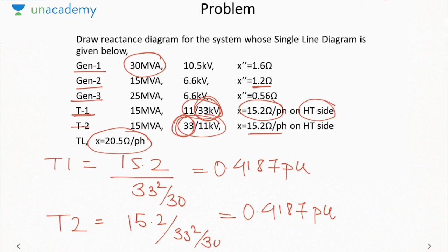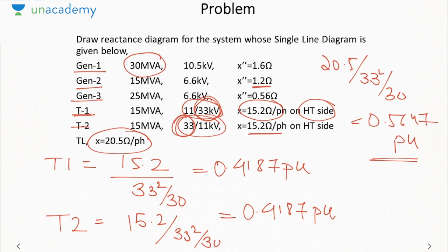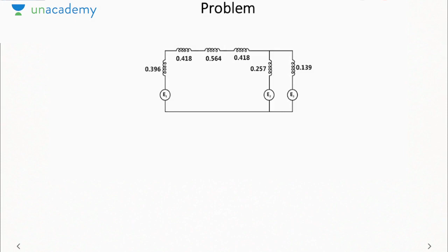So it will be simply 20.5 divided by 33 square by 30. So how much will this come out to be? It will be 0.5647 pu. So this way you have to calculate the per unit impedance on a suitable base for each and every component in the power system. Then you must interconnect these components to attain the per unit diagram.